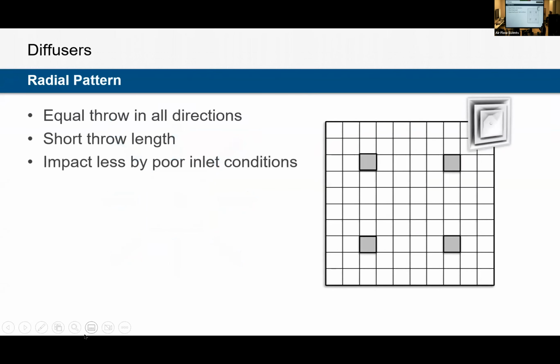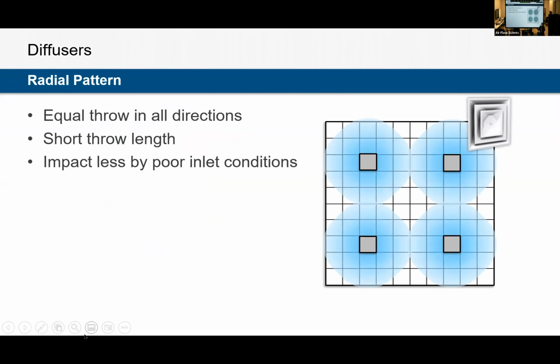The square plaques and square cones are the most common diffuser and the best performing for a couple of reasons. You get really nice 360-degree airflow pattern out of them. Usually have pretty short throw distances, so we're not as concerned with drafts with this type of diffuser. Less impact by poor inlet conditions. So if we've got tight elbows, maybe some flex duct on the inlets, they're a little bit more resilient to that. And then they are also the best for turn down, as Tom was mentioning.